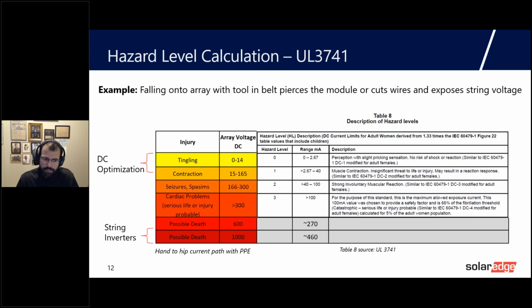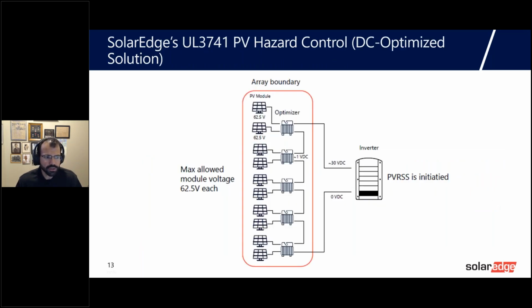But solutions without MLPE, which keeps the array at 1,000 volts even after rapid shutdown, result in around 460 milliamps, well beyond the chart. This is why folks always ask, do we need extra protection like the UL 3741 racking? We do not, because our system, like I explained, stays within hazard level 1.